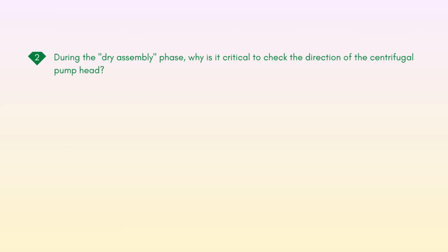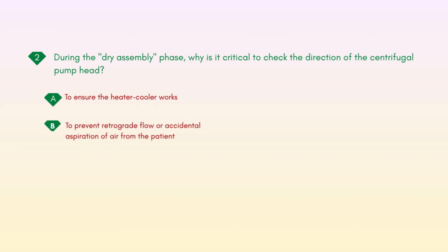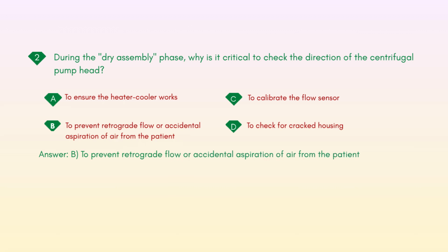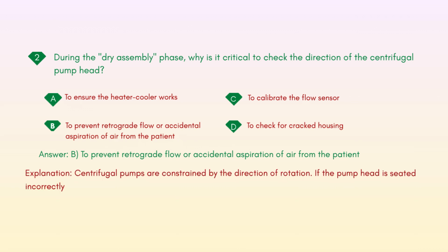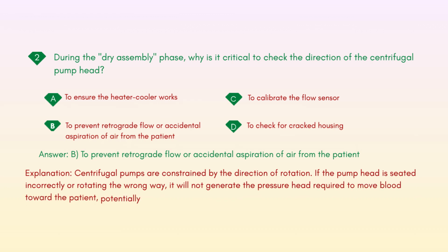out. During the dry assembly phase, why is it critical to check the direction of the centrifugal pump head? A. To ensure the heater-cooler works. B. To prevent retrograde flow or accidental aspiration of air from the patient. C. To calibrate the flow sensor. D. To check for cracked housing. Answer: B. Explanation: centrifugal pumps are constrained by the direction of rotation. If the pump head is seated incorrectly or rotating the wrong way, it will not generate the pressure head required to move blood toward the patient, potentially causing a backflow of blood or air.